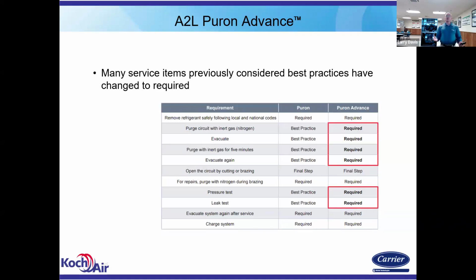And when you've made your repair, you pressure test it, where before that was a best practice. Of course, after you braze something in or do a mechanical fitting, you want to pressure test that and make sure it doesn't leak. With Puron, it was not a requirement. It really should have been, but it is now.